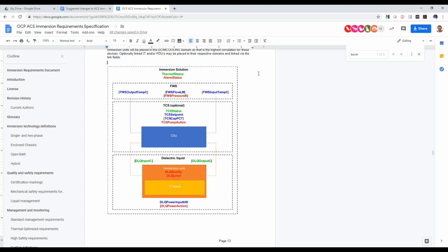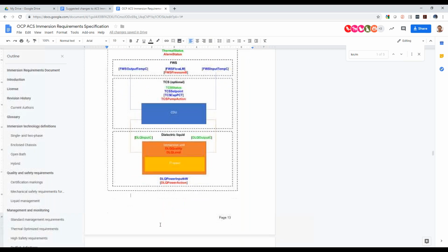What you see here is all the values required for a system, and the colors relate to the level of requirement. Anything green is required anyway for each system. The red ones are for a high safety system, and the blue ones are for a thermal optimized system. So for the entire system, for one immersion solution, it's required to have a thermal status, and if you want a high safety system, it's required to have an alarm status. This triggers down a bit.